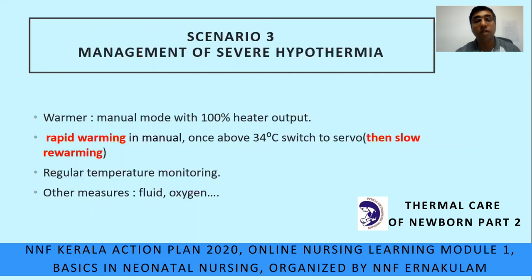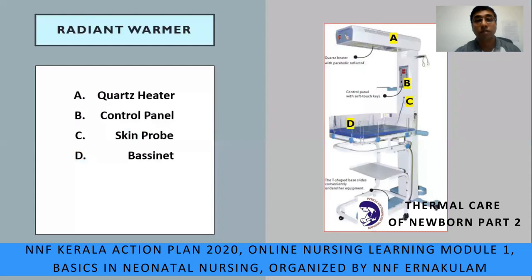We will be discussing the warmer in the following slides. For general viewers: A is the quartz heater, which provides the radiant heat. B is the control panel, which displays the temperature and has the control switches. C is the skin probe, which is attached to the baby and records the infant temperature. D is the basinet, which is used for placing the baby.